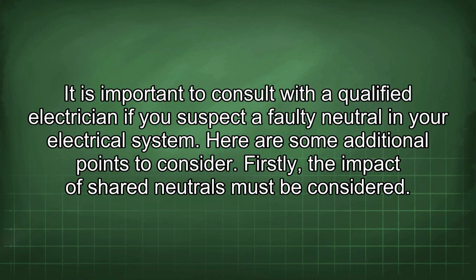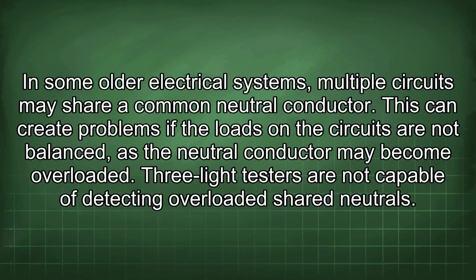Firstly, the impact of shared neutrals must be considered. In some older electrical systems, multiple circuits may share a common neutral conductor. This can create problems if the loads on the circuits are not balanced, as the neutral conductor may become overloaded. 3-light testers are not capable of detecting overloaded shared neutrals.